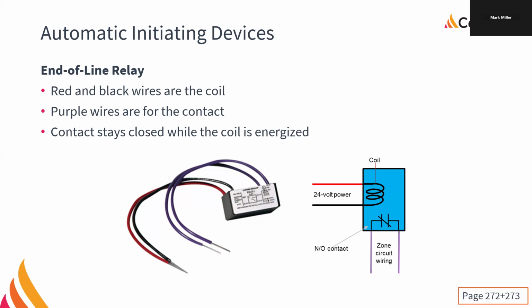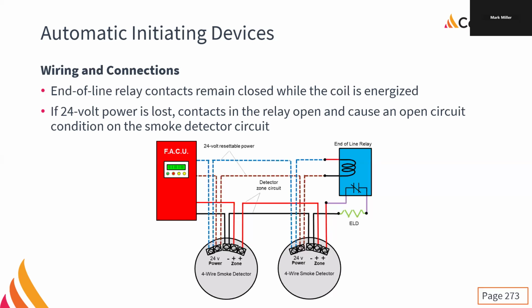When we have the 24 volt DC going to the four-wire smokes, we're going to be able to get the end of line on the initiating zone, and it's going to work. And there is the wiring diagram. Okay, so we can see that the blue and maroon, maybe burgundy, is the 24 volt power. It goes to the end of line relay. It goes onto the coil. Then we have the red and black, that's the initiating zone that goes to all the smoke detectors. It might be going to heats and pulls as well. That is fine.